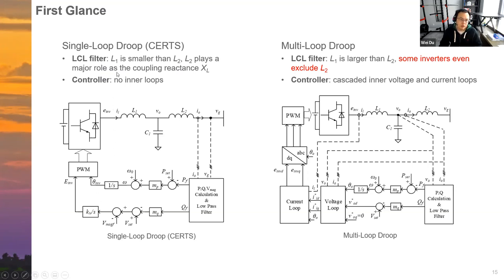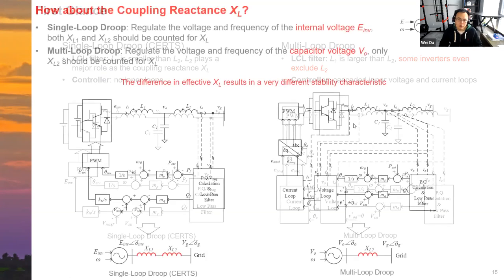And we have an LCL filter. Typically, L1 is much smaller than L2, because we think L2 can play a major role as a coupling reactance, and we know the importance of this coupling reactance. And the right side is a multi-loop droop control. It also has an LCL filter and the inner droop controls, but also the cascaded inner voltage and current loop controls. And I noted that in the literature, typically L1 is much larger than L2. Sometimes in the paper they even do not have L2, they only have L1. But this probably doesn't help you understand those two controls too much. So we need to go further.